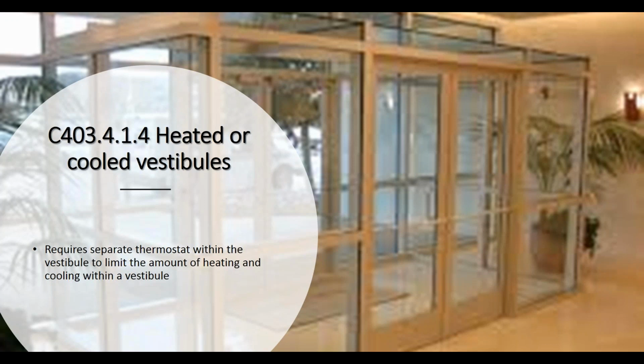They're this energy saving measure to keep this big, huge swoosh of air between the doors from opening. And it wasn't really meant to be heated or cooled, but people are doing it. Okay, you're going to do it? Fine. Then let me just tell you that now it says if you're going to heat it, it just puts limits on it. So if I heat it, you have to provide a control that shuts off the heat when the air outside is more than 45 degrees. It's not saying you can't heat it, it just limits it.